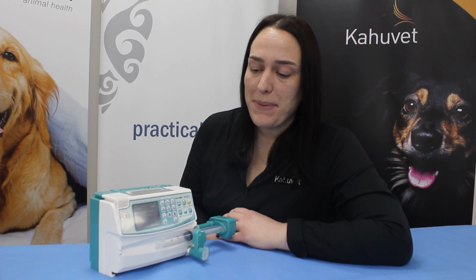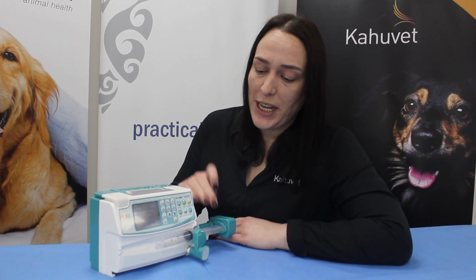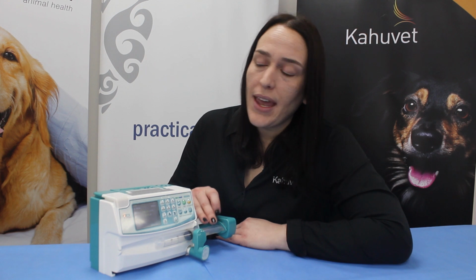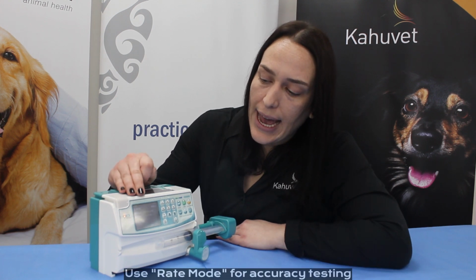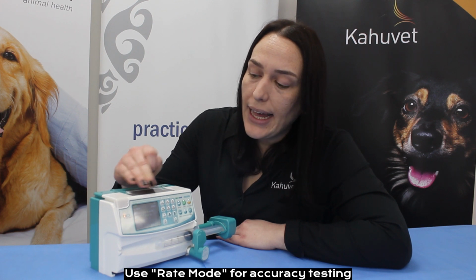For the final part of this instructional video, we'll show you how to test your pump for accuracy to determine that the pump is delivering your syringe contents to your patient as per the settings you've entered on the pump. We can do this with a 20ml Luer lock syringe, and what we've done with our settings is our rate mode has been set to 200 mils per hour, a little bit high here just for the purposes of this test to get through the syringe contents.